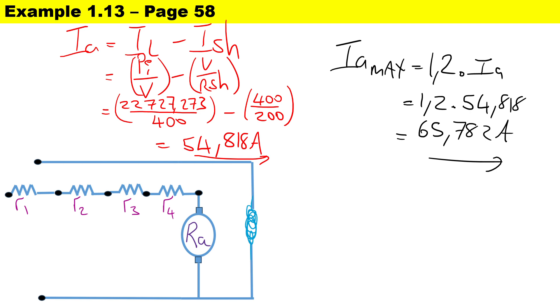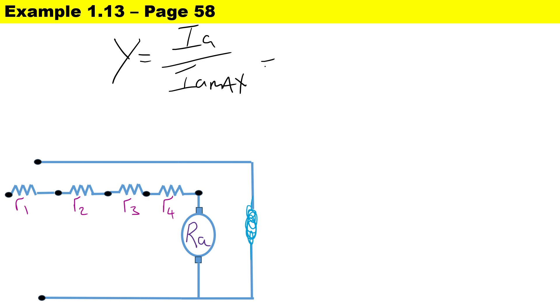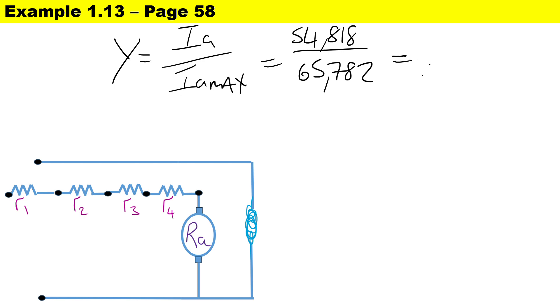Now we can calculate the ratio represented by the letter y. It is Ia over Ia_max: the normal armature current is 54.818 and the maximum armature current is 65.782, giving us a ratio of 0.833. This ratio is important for all our other calculations, and as a reminder there are four elements.